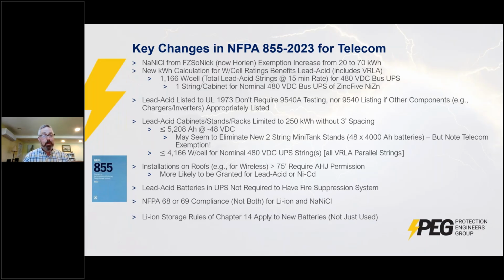But there's a tradition or practice, for decades, that people have built their own battery plants by purchasing listed chargers, listed rectifiers, and so forth, and inverters, and just regular batteries. So if you can use a listed battery and all the other components are listed, you can put together your own system. You don't have to go through the system level 9540 process that looks at integrated type systems. So that's a unique twist to the standard that's specifically addressing the way lead acid batteries have been used.